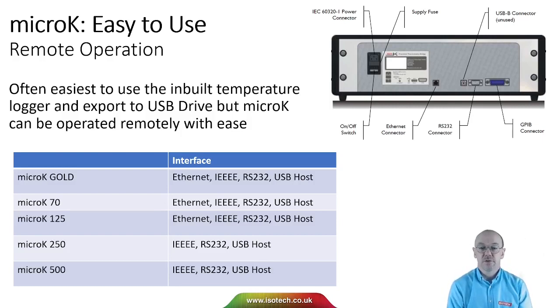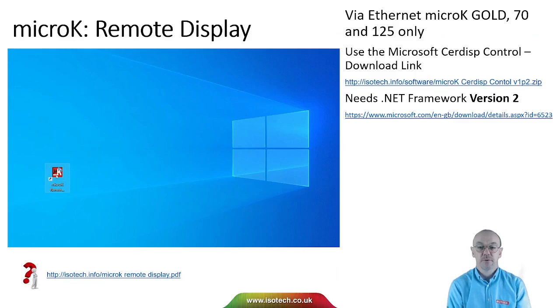It's often easiest to use the inbuilt temperature logger and just export the data on USB, or you can operate the MicroK remotely. The MicroK GOLD, 70 and 125 has Ethernet, as well as IEEE, RS232 and USB connections. MicroK 250 and 500 don't have Ethernet, but they do have IEEE, GPIB, RS232 and USB. And with the MicroK GOLD, 70 and 125, it's nice that we can use a remote display.